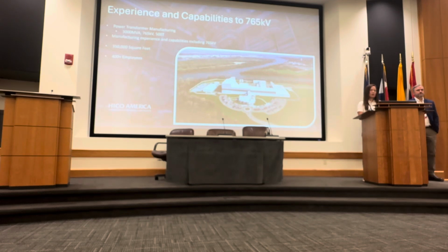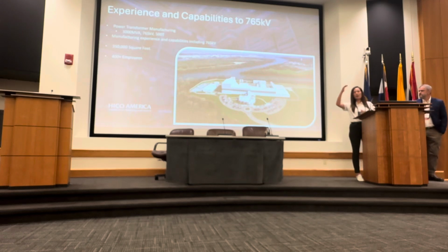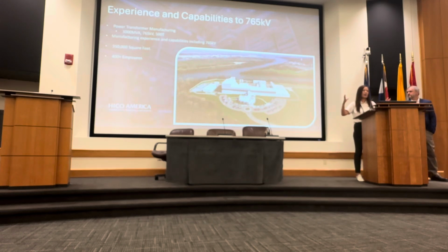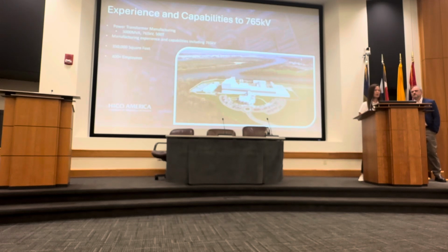My experience is with EHV, very high voltage transformers. It's very important to have domestic manufacturing, especially for such a big country. With 765 kV, you see our facility has a very high ceiling. You need a very big capability to pick up the active parts, the core and the coil, because those are very heavy things. You have to have a very good engineering process, manufacturing process, and most important is the management process.